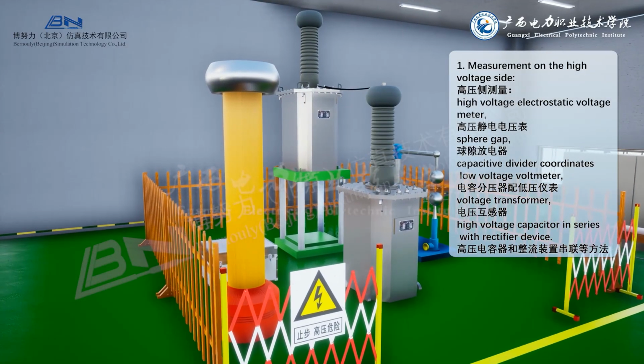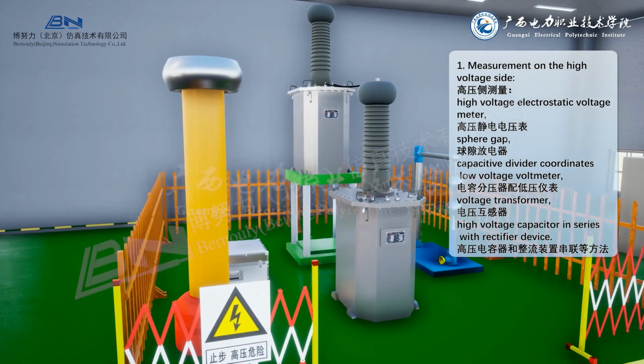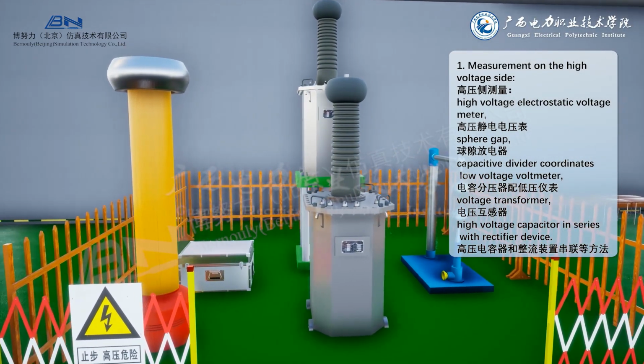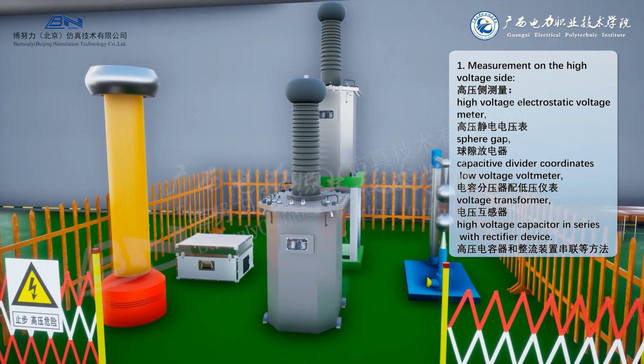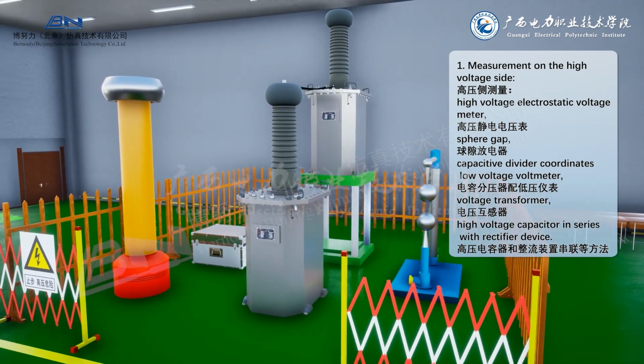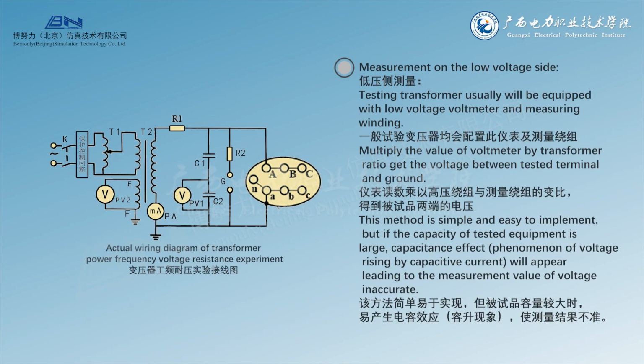Measurement on the high voltage side: high voltage electrostatic voltmeter, sphere gap, capacitive divider with low voltage voltmeter, voltage transformer, and high voltage capacitor in series with rectifier device. Measurement on the low voltage side: the testing transformer is usually equipped with a low voltage voltmeter and measuring winding. Multiply the value of the voltmeter by the transformer ratio to get the voltage between the tested terminal and ground. This method is simple and easy to implement, but if the capacity of the tested equipment is large, the capacitance effect, a phenomenon of voltage rising by capacitive current, will appear, leading to inaccurate voltage measurement.